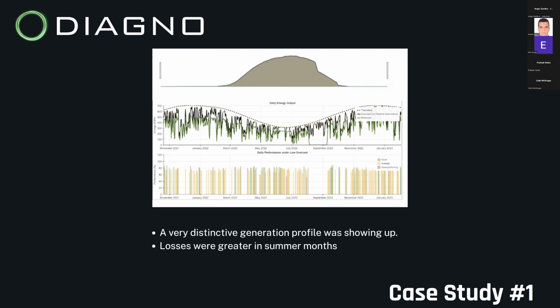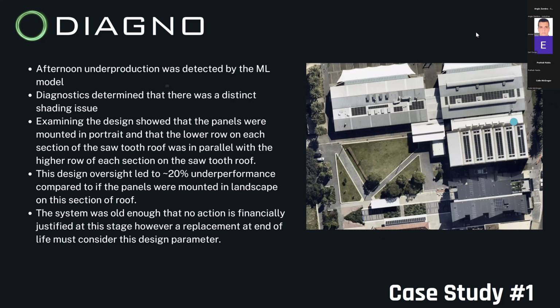Here's one where a very distinctive generation profile was showing up. You can see in the afternoon that double knee happening every day, and losses were greater in the summer months. The diagnostic determined this was due to shading. You can see below there's a sawtooth roof, and that's where the shading was originating from. So we were able to detect that.